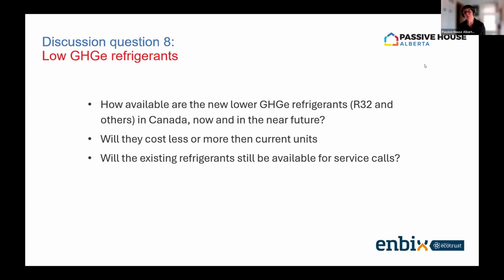That's what I got. Rod, you had some comments as well. Yeah, we decided to switch from VRF DX coils and go all hydronic because they're just a little too sensitive. That gets all the refrigerants out of our buildings, so we can buy these self-contained air-to-water units and keep them outside. The most problems we've had with leakage on any refrigerants has been from on-site work versus the units we actually buy. I find hydronic more versatile for the systems we're looking at.